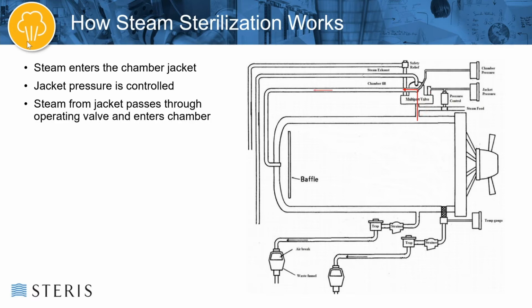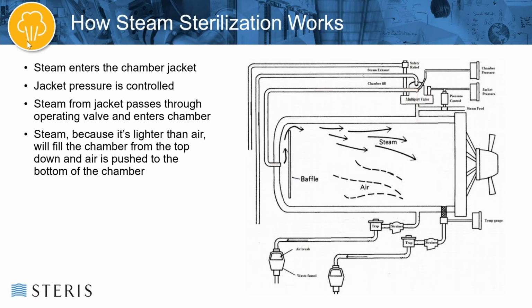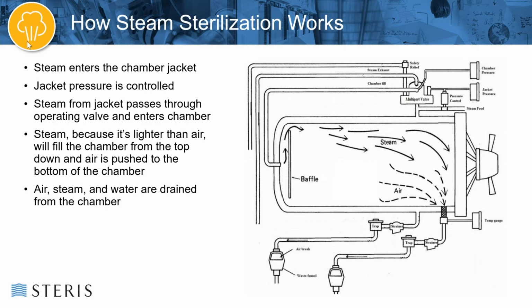And then steam from the jacket goes through this line and enters the chamber behind the baffle. Once it goes into the chamber, it will often go to the top of the chamber, and the chamber will become stratified with steam at the top and air at the bottom. Because steam is lighter than air, it'll fill the chamber from the top and push the air down to the bottom of the chamber. As the initial stages of the process go on, air, steam, and water resulting from condensed steam are drained from the chamber down through the system drain.